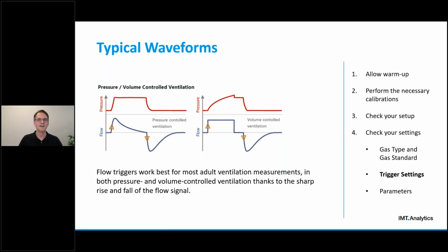So here on this slide, you can see typical flow and pressure waveforms on the left-hand side for pressure-controlled ventilation, and on the right-hand side for volume-controlled ventilation. And in both cases, the flow signal typically has very rapidly rising and falling edges at both breath transitions. And also, and this is actually what we just learned earlier that is most important for a good trigger signal, right?